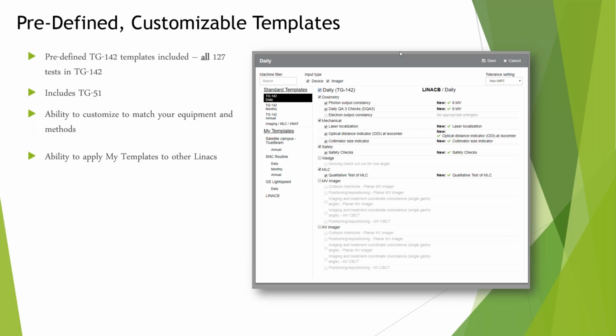The system has predefined customizable templates. All 127 tests in TG142 are included, and it also includes TG51. And we have the ability to customize those templates to match our equipment and our methods. Once you create your template, you can apply it to other Linacs. So as we completed our Elekta, we applied the main core tests to the Varian Linac, and then slightly modified them based on the Linac differences between the two vendors.